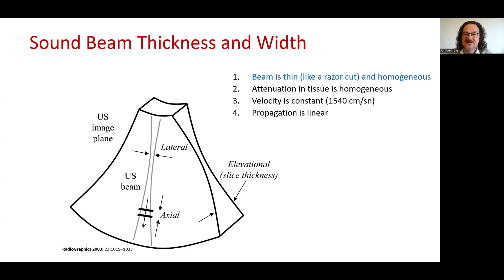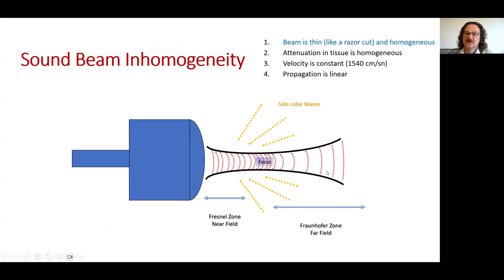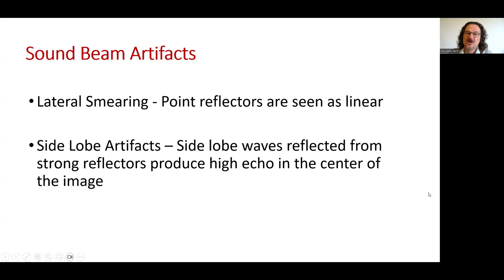The ultrasound device assumes the beam is thin and homogeneous, but there is a slice thickness and the sound beam is not homogeneous. Sound beam artifacts include lateral smearing, where point reflectors are seen as linear, and sidelobe artifacts, where sidelobe waves reflected from strong reflectors produce high echo in the center of the image.